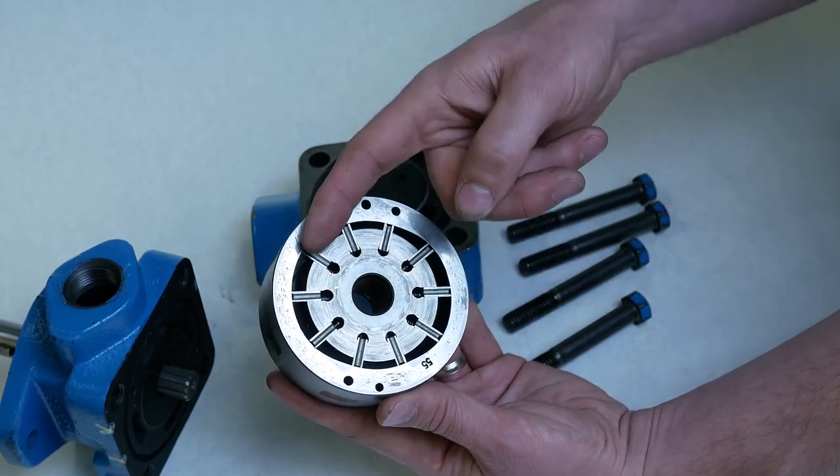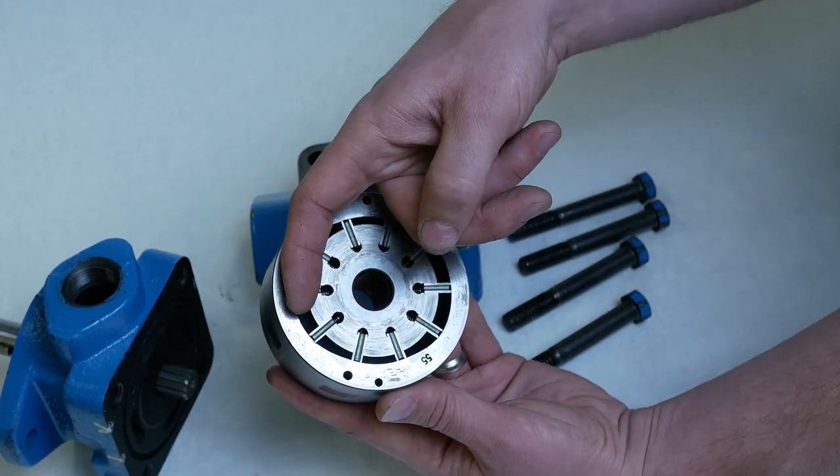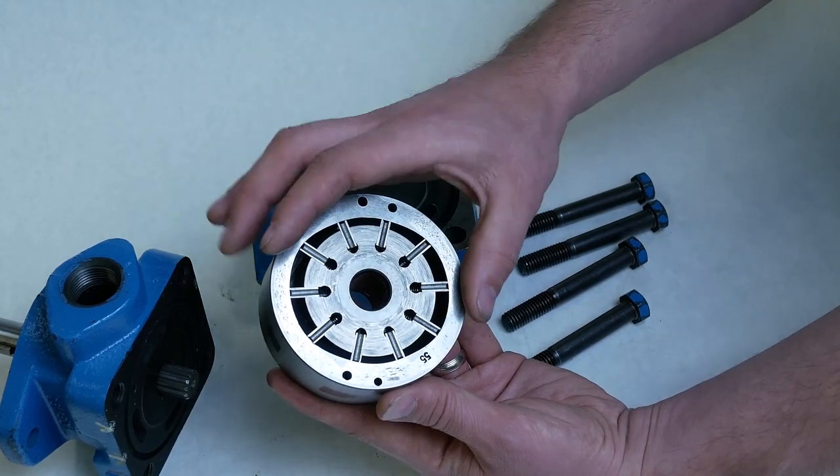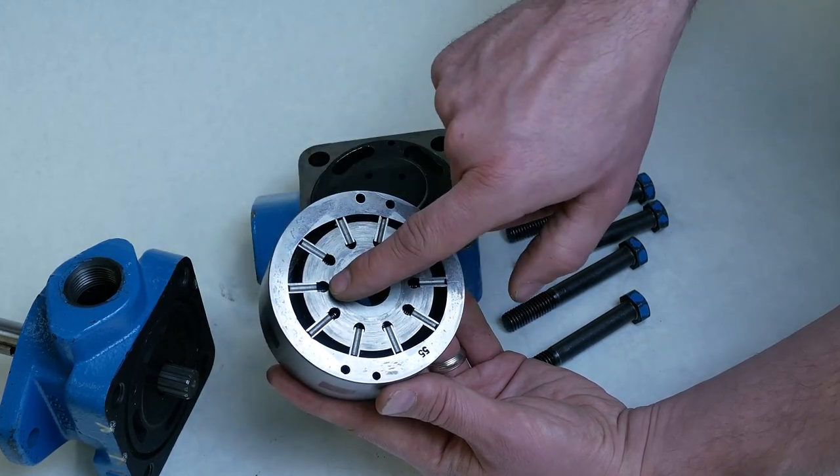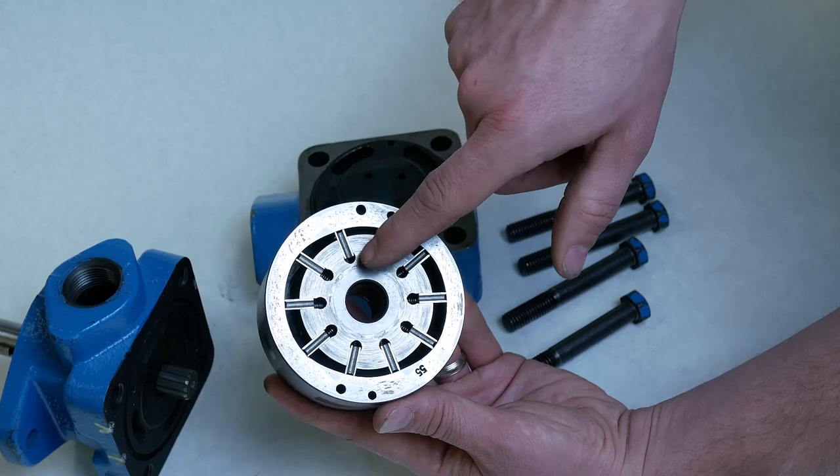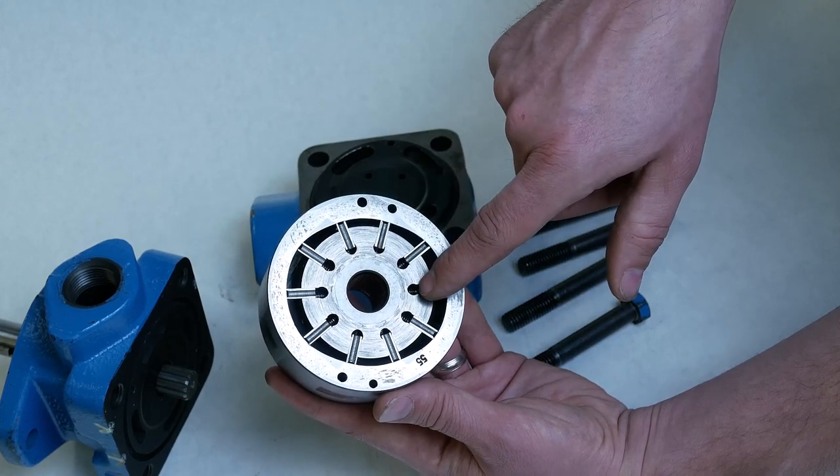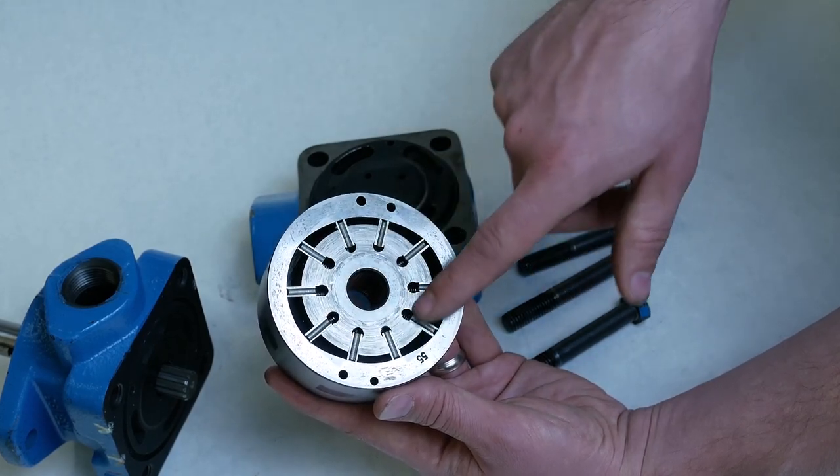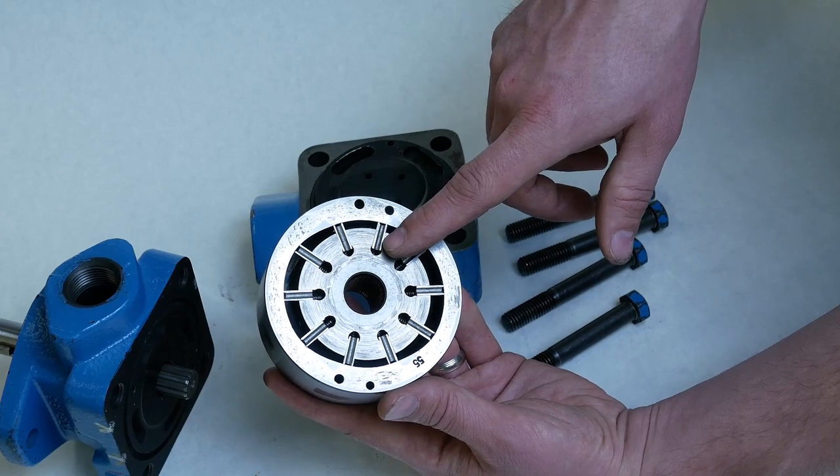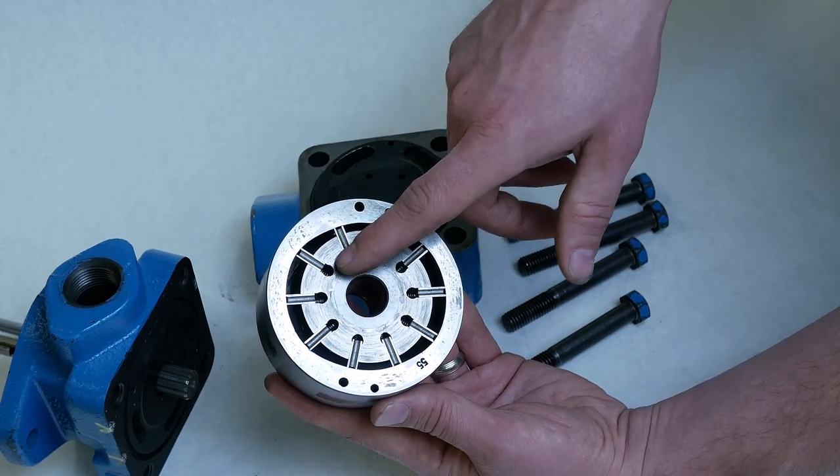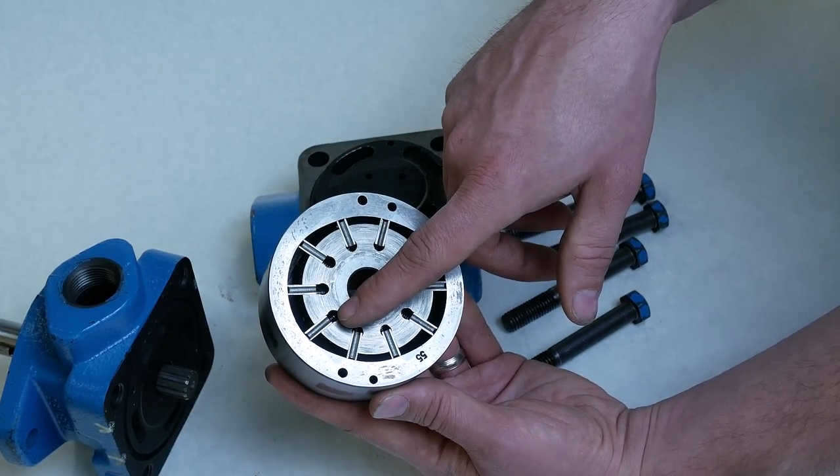So this is what's allowing oil flow to come in and immediately start movement. We don't need a minimum RPM, and this is an indicator when they have springs behind them that either they want the pump to run at a really low speed or it's a motor because then we have to be able to start delivering torque at zero RPM and accelerate from there.